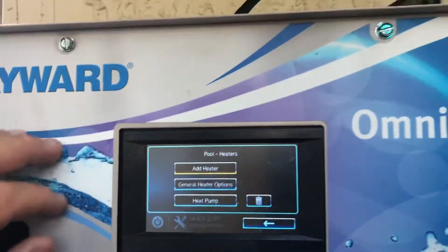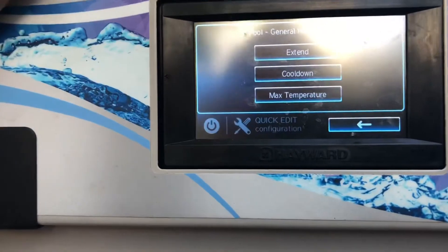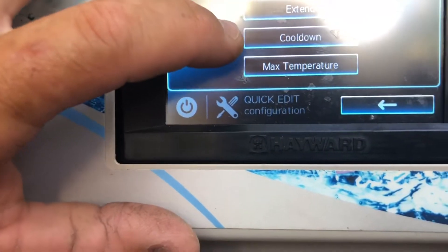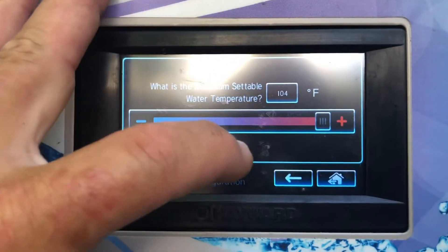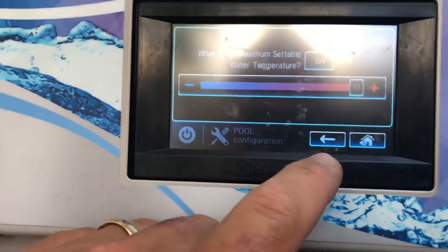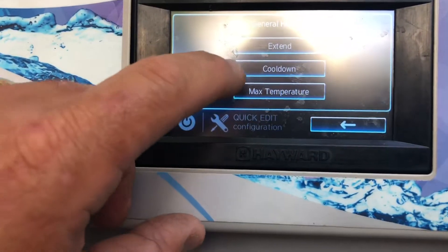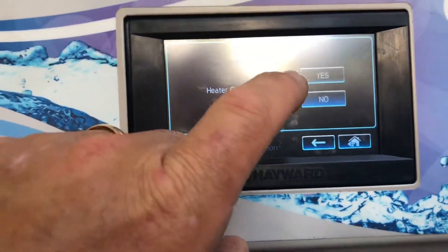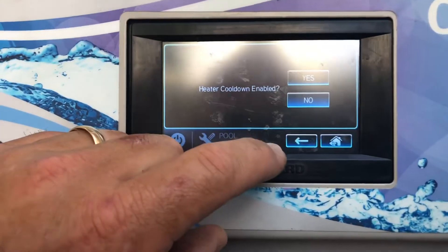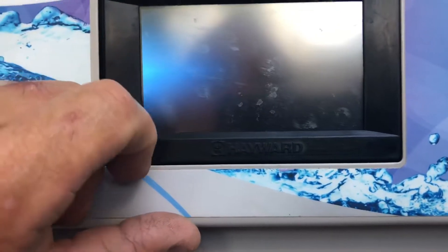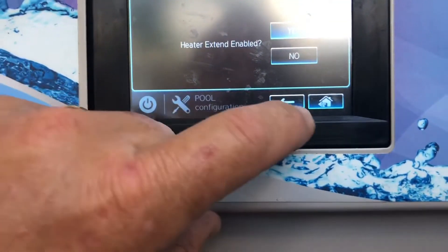That's basically how you add a heater to your Hayward OmniLogic. Let's go into the general heater options and see what's in here. This is where you can set an extended time, a cool-down temperature, a max temperature — if you don't want it at 104 you can slide the bar up and down. You can set your cool down; if you do select cool down it may stay on running for about three to five minutes while it does a cool-down cycle.